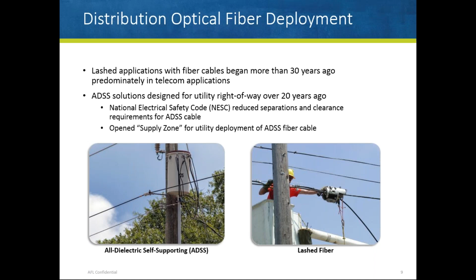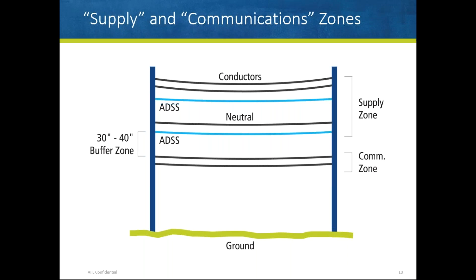So here's a quick graphic to take a look at what we are talking about. As utilities, I'm sure, are aware, supply zone would be your conductors, but also your neutral. And this NESC code adjustment shows you could easily put ADSS either above or below your neutral in that supply zone. Your communication zones would be your telecom space for copper cables and fiber cables, typically lashed, and that buffer zone, depending on your distribution voltage, would be in the 30-inch to 40-inch range to keep those sections safely separated for line work. So that really sets up our further discussion in the distribution space.